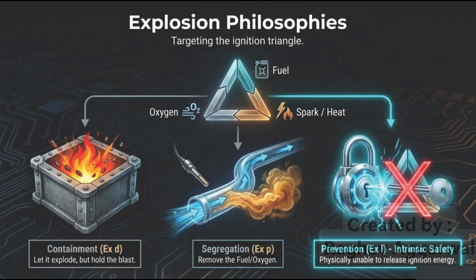The third approach is prevention, identified as Ex i, which stands for intrinsic safety. Rather than containing or isolating hazards, intrinsic safety prevents the release of sufficient ignition energy in the first place. This preventive approach targets the ignition source directly by limiting energy levels. Different protection philosophies attack different parts of the problem, but all aim to prevent catastrophic events in hazardous environments.